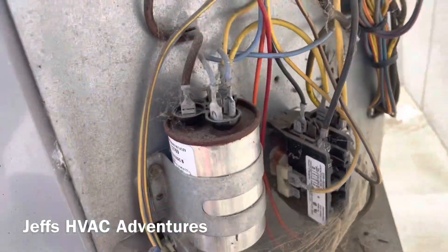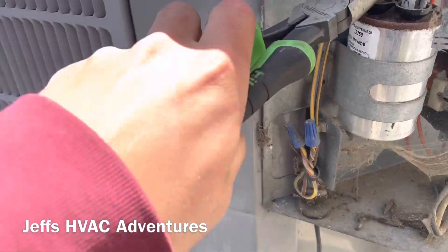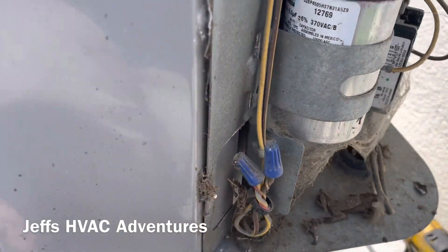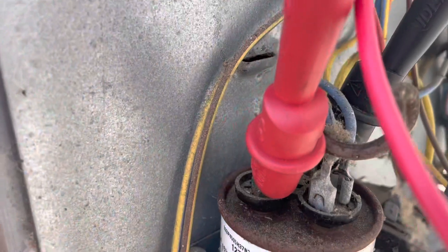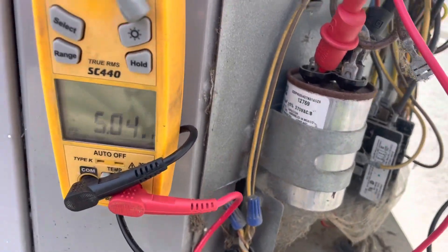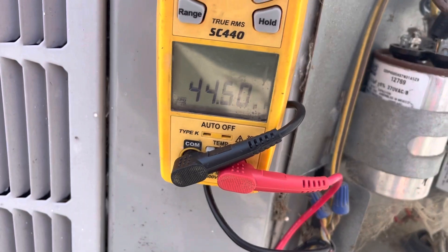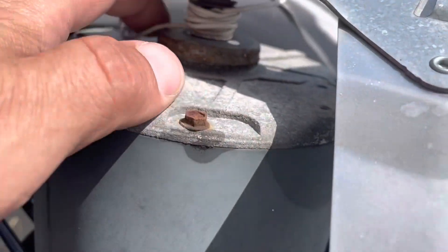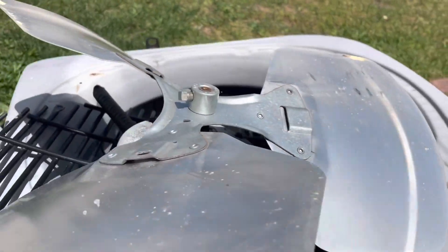Before we go much further we're going to check this capacitor. Even though the compressor started, we could have an issue on the fan side. That wire was caught in there but it did kind of spin freely. It's a 45/5 microfarad capacitor — we're reading 5 microfarads on the fan side. Let's check it on the hermetically sealed side: 44.5. So this capacitor is good — we have a bad motor. Somebody dropped their earbuds in there and they got all caught up in this fan, so that's probably why this fan doesn't work.